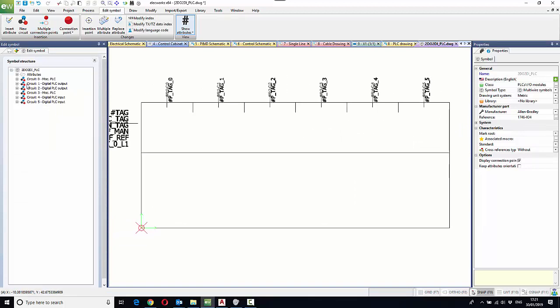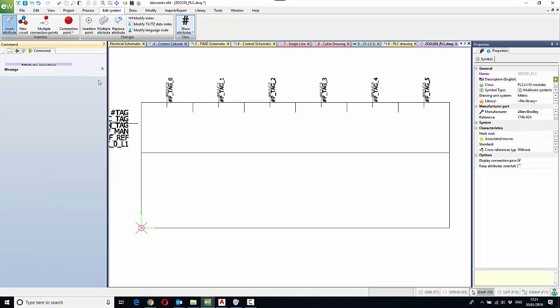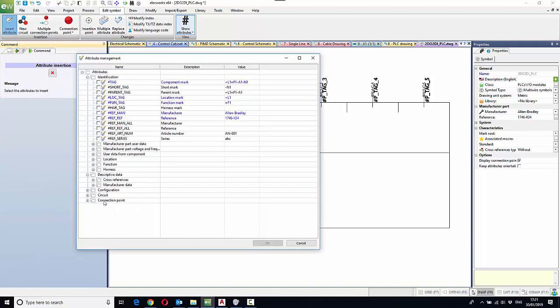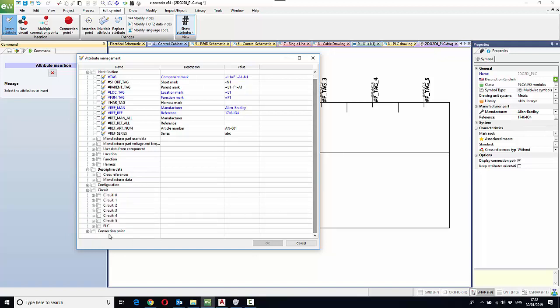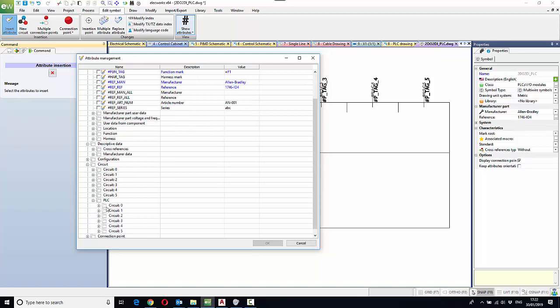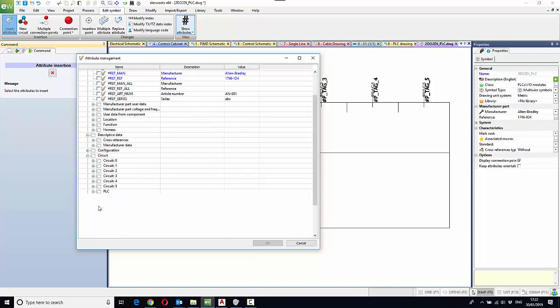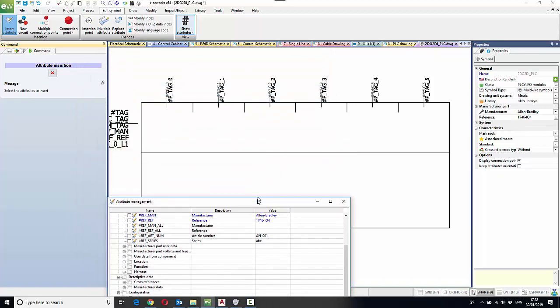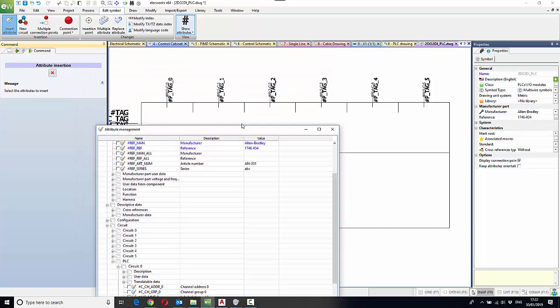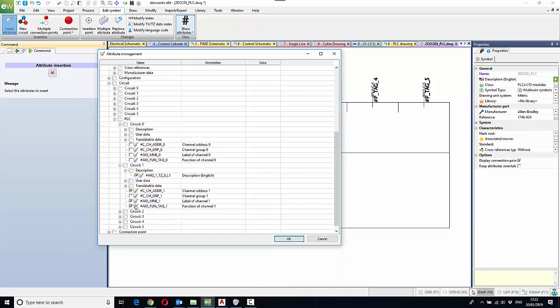For each one of these connections, we can also add additional attribute information. So for example, for the digital PLC output, if we go down to the circuits connections, circuit one as an example. So you can be selective when it's a PLC and add additional pieces of information. I'm just going to add the description and the channel address in this particular instance.